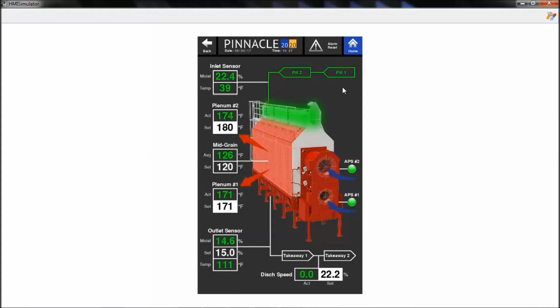If we come back to our control and start plenum number 2, it'll purge, and we'll be able to see it's going through its purge right now. It hasn't turned on yet, but after a few seconds, this turns red, which indicates that the burner has ignited and we have a positive signal.